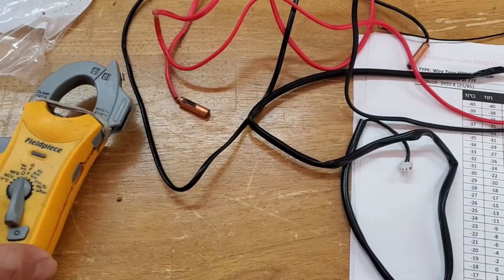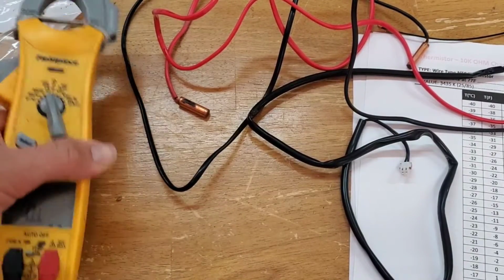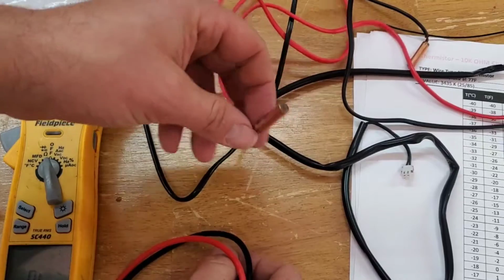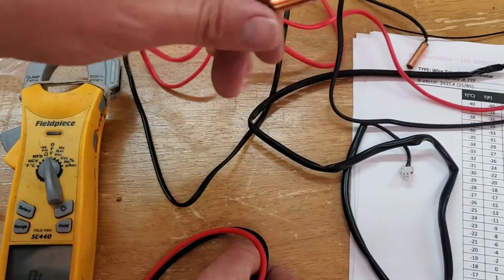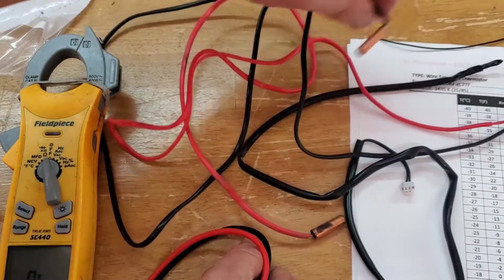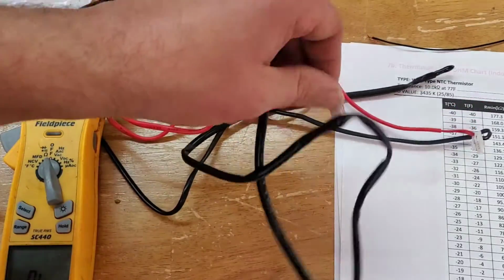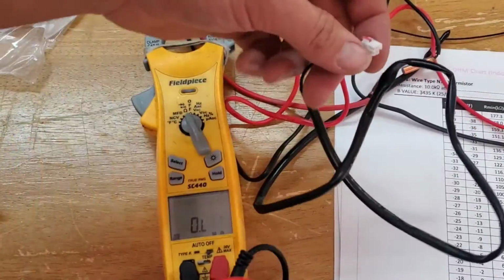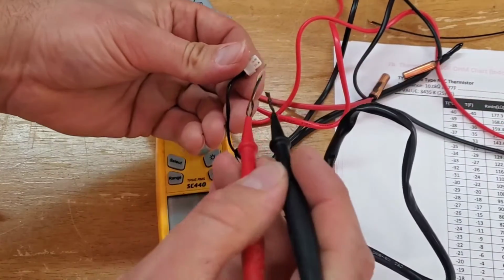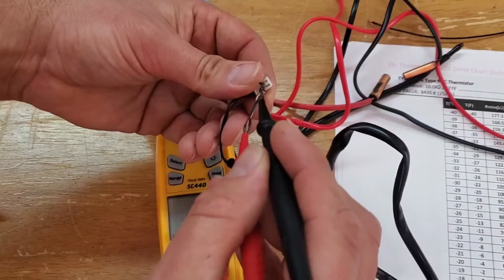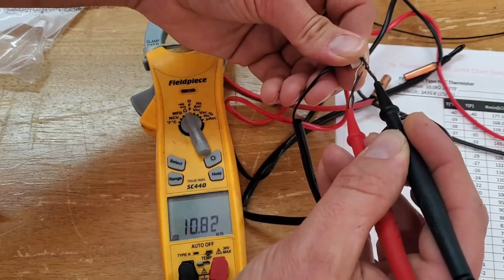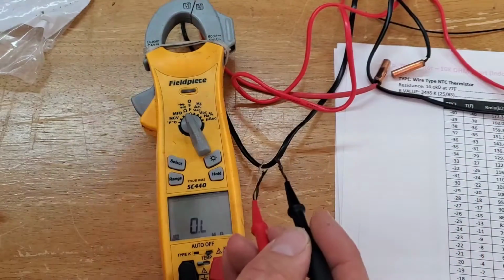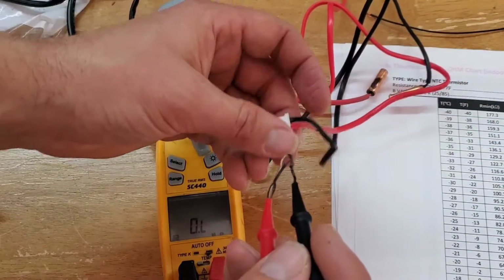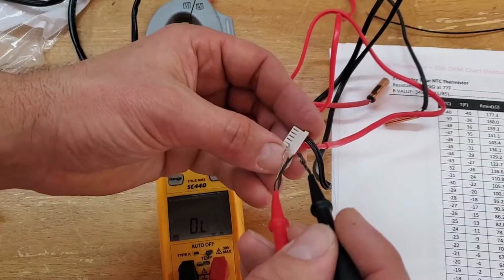Now we are going to test the sensor for the ducted air handler. Okay, and this indoor sensor right here measures the indoor heat exchanger. This one does as well. And then you've got this indoor ambient sensor. Now it's 71 degrees in here, so keep that in mind. We're going to measure this sensor first, and this is a 10 kilo ohm. See, 10.8. All right, and since this is the same temperature in here, they should all read the same.